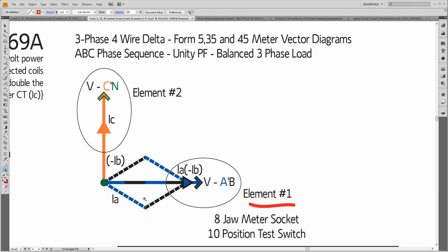So at a balanced three-phase load, the magnitude of this current ends up being 86% of what they would be added together directly. We won't worry about that other than it's 86% at 240 volts. Over here, it's a full current value at 208, and so I have 86% of the voltage here and full current. Over here I have 86% of the current and full voltage. And so in this 2-element meter with that 3-phase load, I'd get the exact same amount of torque out of this element as I would this one. And so that's something that's pretty cool in this one.